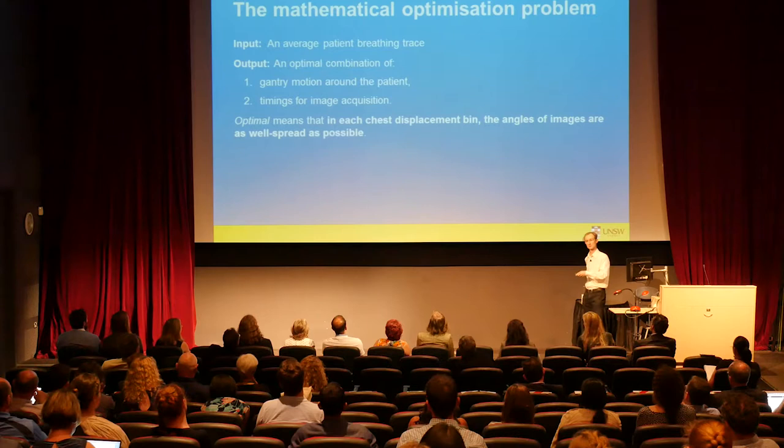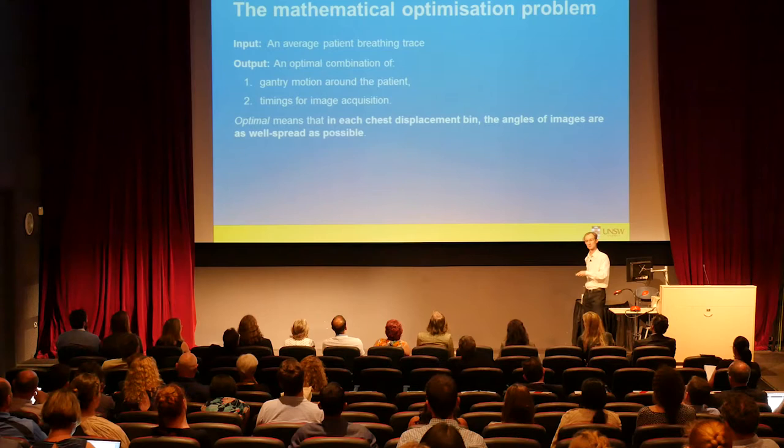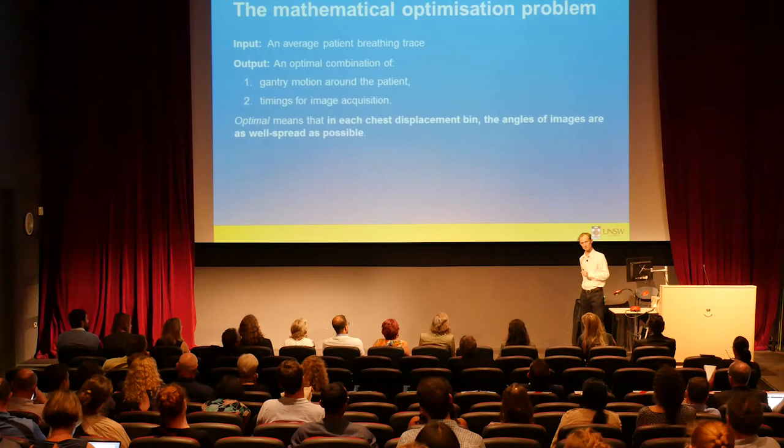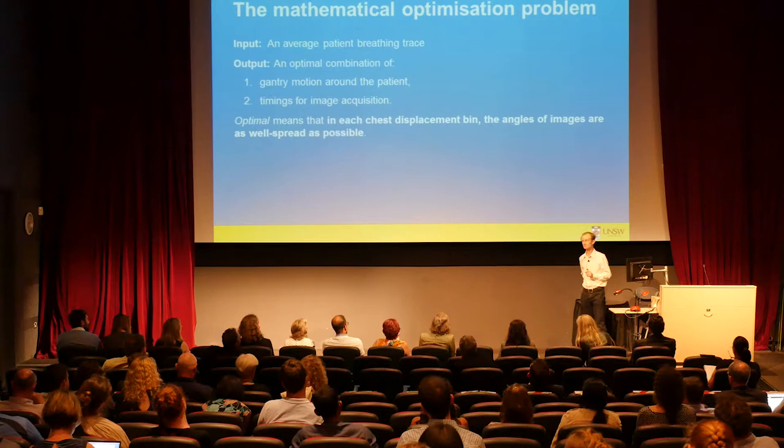The output is: how does the gantry move around the patient? Does it cruise around uniformly, or — since these machines can accelerate and decelerate very rapidly — should we take advantage of that to improve images? Also, when you pulse with the x-rays to image the patient, that timing is under your control and should be optimized. The goal is that in each bin — for example the red bin — we want a well-spread collection of angles.